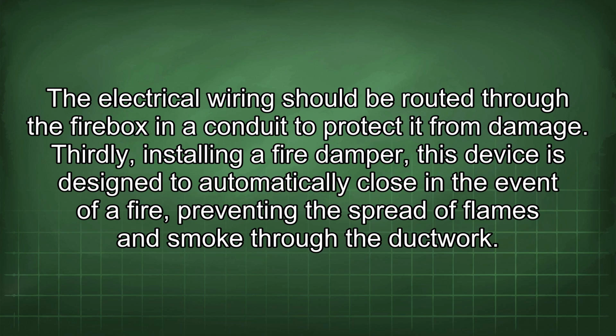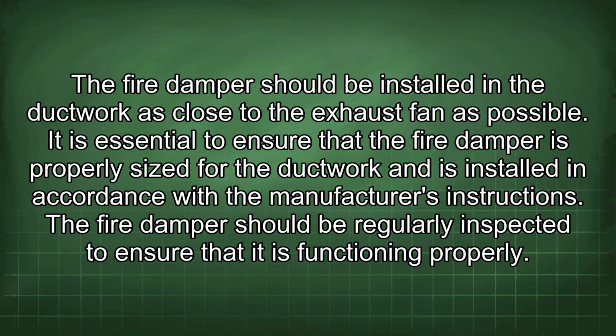Thirdly, installing a fire damper. This device is designed to automatically close in the event of a fire, preventing the spread of flames and smoke through the ductwork. Fire damper should be installed in the ductwork as close to the exhaust fan as possible. It is essential to ensure that the fire damper is properly sized for the ductwork and is installed in accordance with the manufacturer's instructions. The fire damper should be regularly inspected to ensure that it is functioning properly.